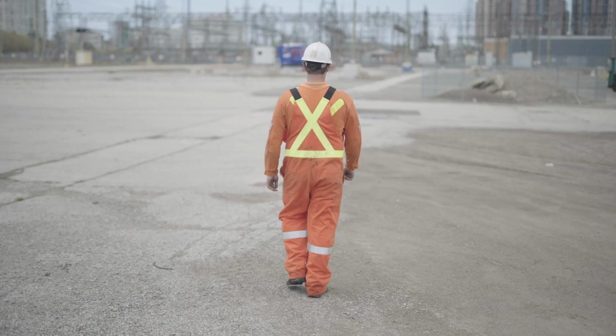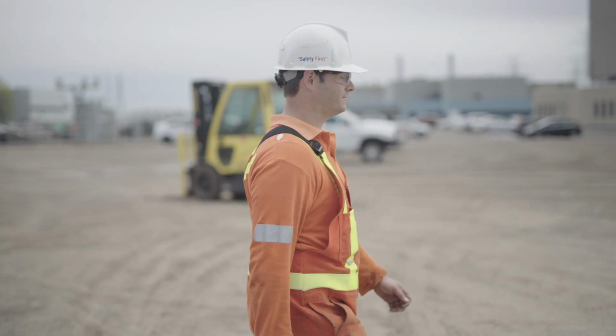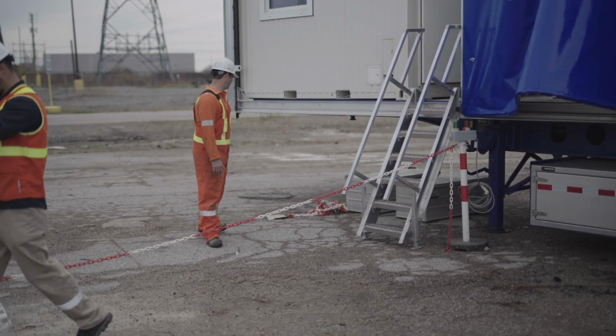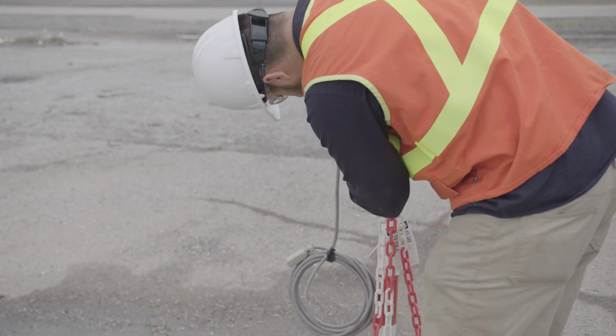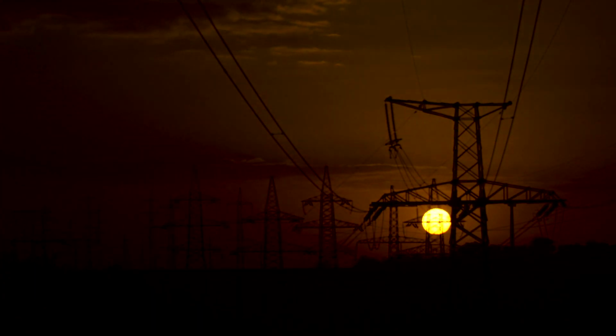Our clients are expecting, when they install a high voltage cable, they have a reliable system. Transmission lines, when they're designed for 30, 40, 50 years, from our experience, they can work much longer. So the idea behind it is supposed to have a defect-free cable when it's installed. However, if you have those latent defects, they eventually will grow to a point that actually become a major issue, causing the cable system to fail.